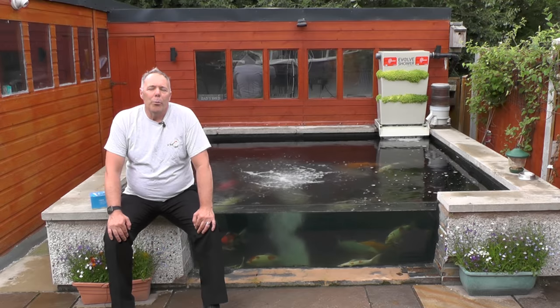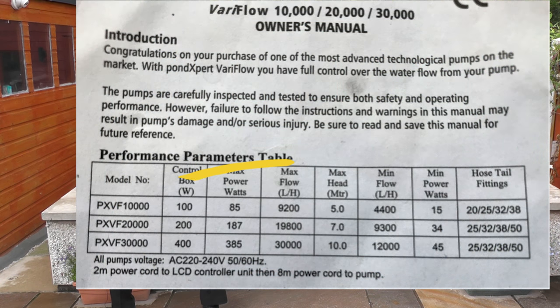But how do you measure your flow rate? People talk about flow rates being what the pump says — I've got a 10,000 litre pump — but the specs on a 10,000 litre pump are based on zero head and running at 100%.